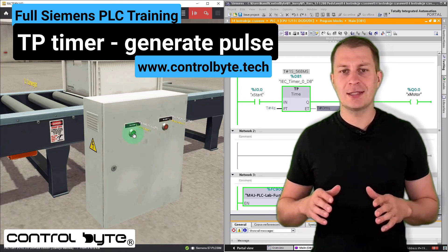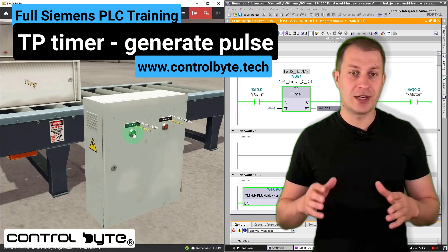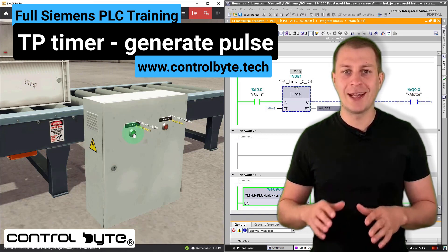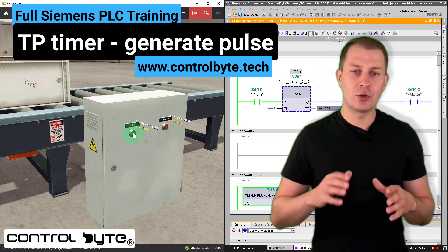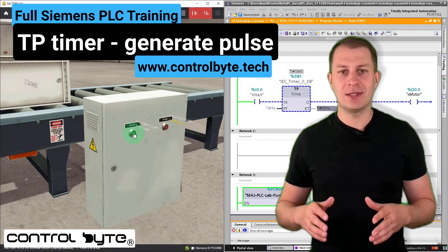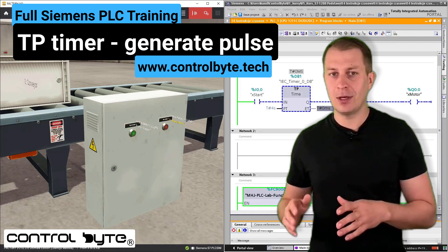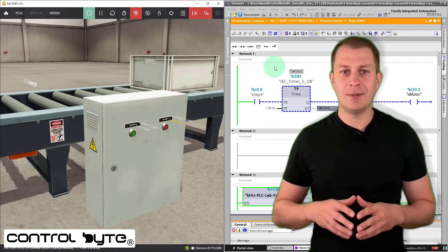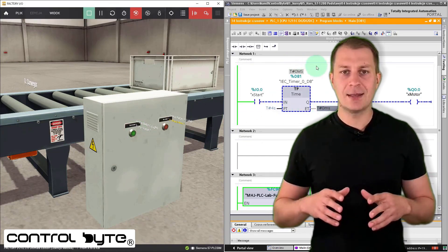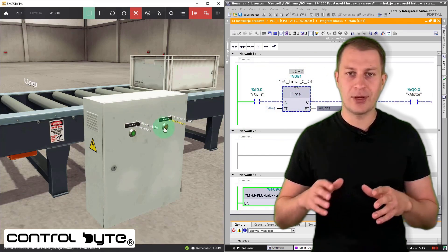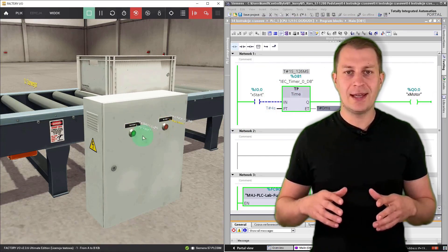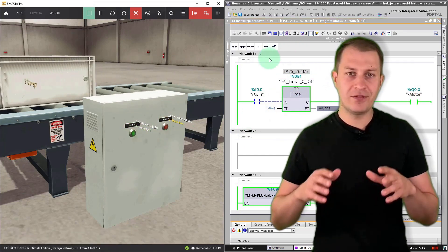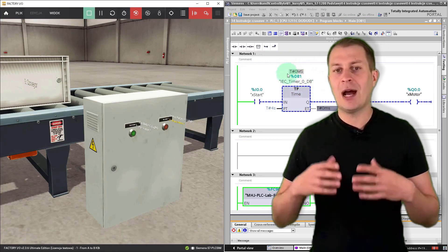We'll discuss the TP instruction first, which allows you to create a signal pulse of a specific duration. This timer type is defined as a DB block in the PLC memory. It consists of two inputs, IN and PT. IN accepts the signal from the last logic operation, while PT takes in the time that defines the duration of our output pulse.